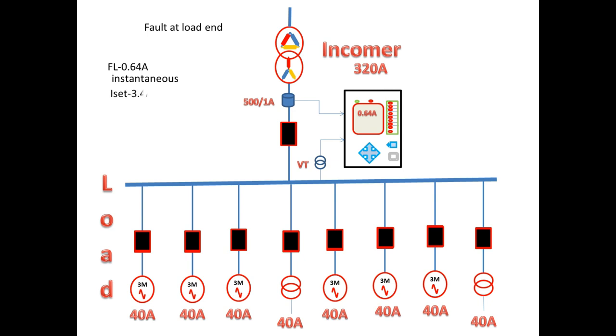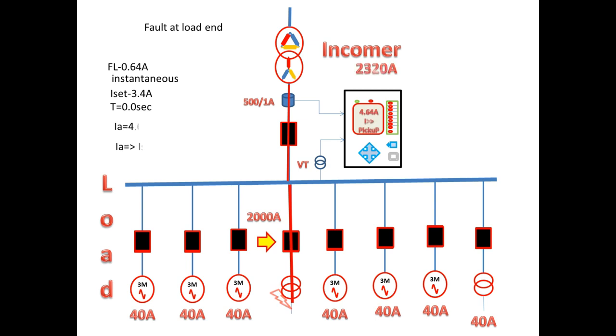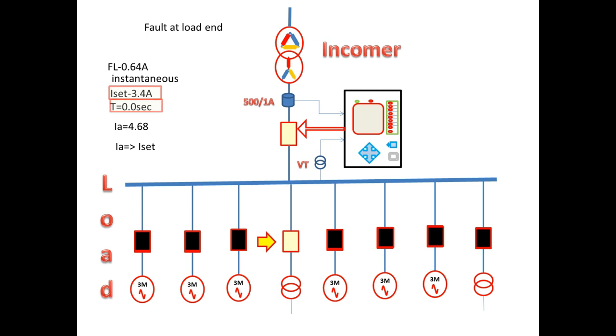So I am going to check now with instantaneous over current. For this I am going to keep ISET equal to 3.4A and trip time is 0 seconds. Now we consider a suddenly heavy fault occurring on one of the outgoing feeder transformers. Due to this fault the fault current taken is 2000A. The actual current of 4.68A flows on the secondary side of the CT, which is greater than ISET.